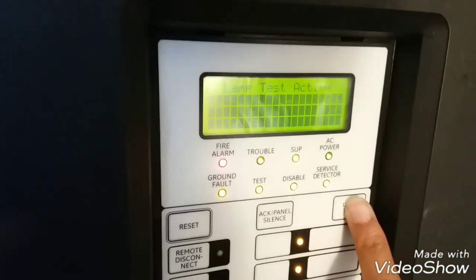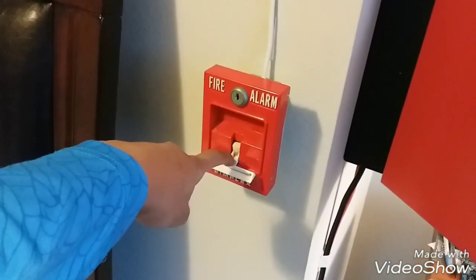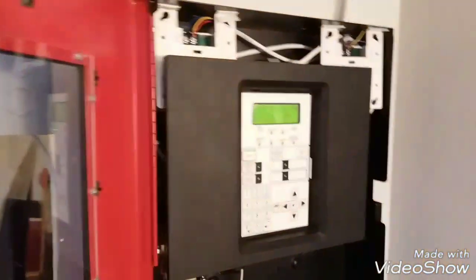The lamp test is like this — you gotta press it again. Yeah, I did that before with Jack. Let's go ahead and test this 4251-20. We'll just go ahead and reset it. 'Emergency evacuation — please proceed calmly to the nearest exit, please remain calm.' Let's go ahead and reset it again. I could have just activated it while talking to you guys and then reset it, but you know — sometimes making simple things complicated. It really be like that sometimes.